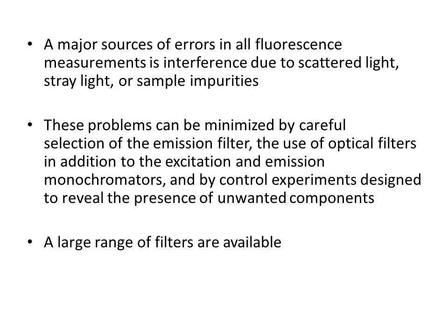A major source of errors in fluorescence measurements is interference caused by scattered light — also known as stray light — or sample impurities. These problems can be minimized by careful selection of the emission filter, together with the use of optical filters in addition to excitation and emission monochromators, and by careful experimental design to reveal any unwanted components present.